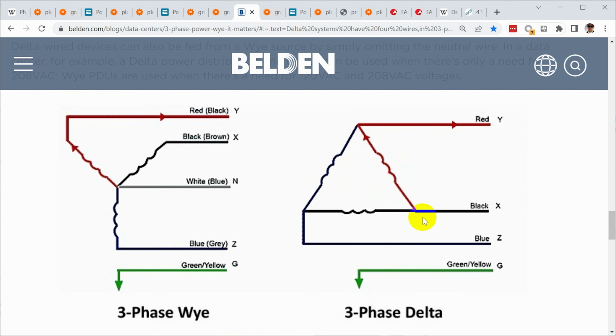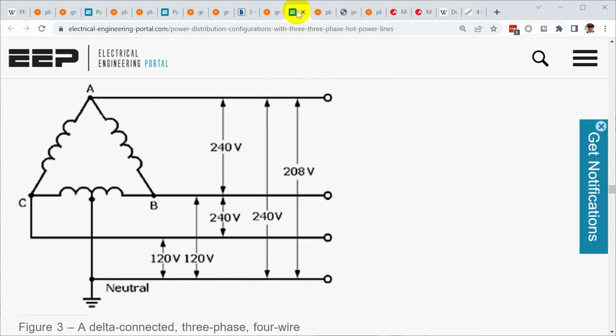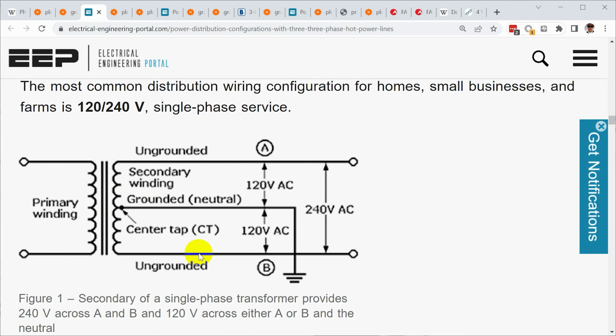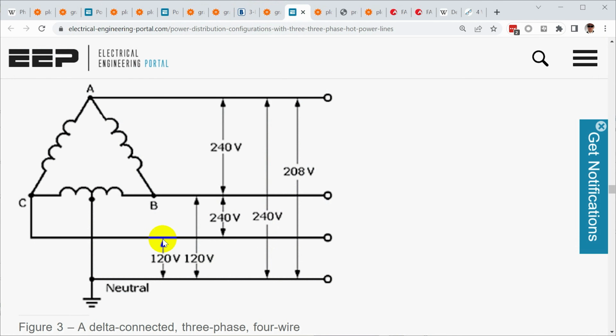What do you do if you have a three-phase delta configured power system and you still need to run 120 volt loads on it? Well, there is a third common configuration, and this is called high leg delta. It's also referred to as wild leg delta or bastard leg delta less commonly, and it is configured like this. You have two of your phases, two of your legs, that are 240 volts AC between them, and you use a transformer that produces a center tapped neutral that's then referenced to ground. So you have this 240 volt phase, exactly the same as the one that you have in residential wiring with the center tapped neutral, where here you can connect 120 volt loads between the neutral and either one of these legs. And you can do exactly the same thing here. You can connect your 120 volt loads between the neutral and either C or B.